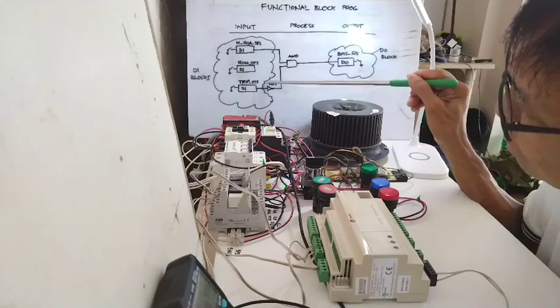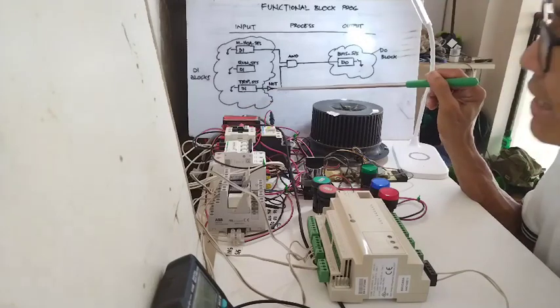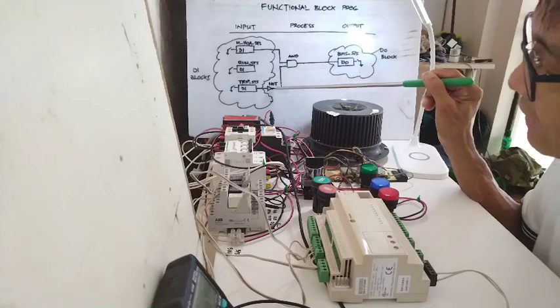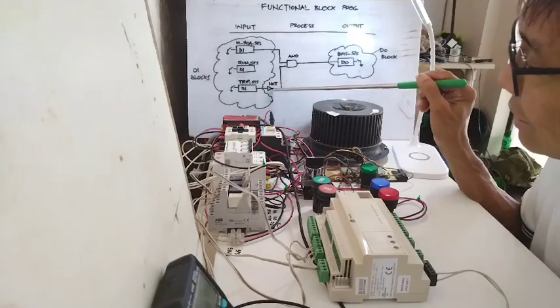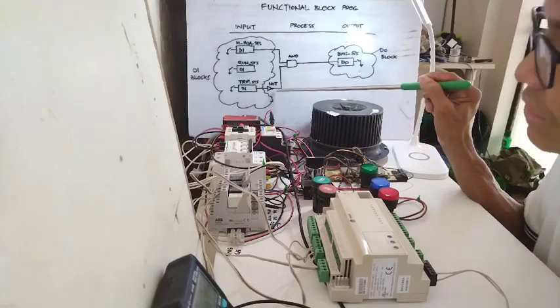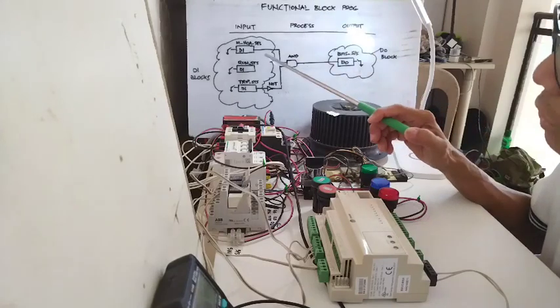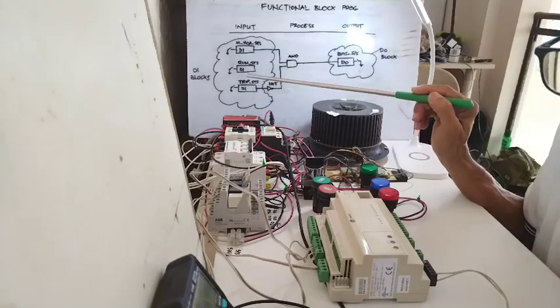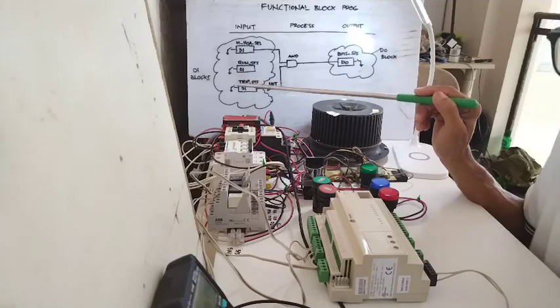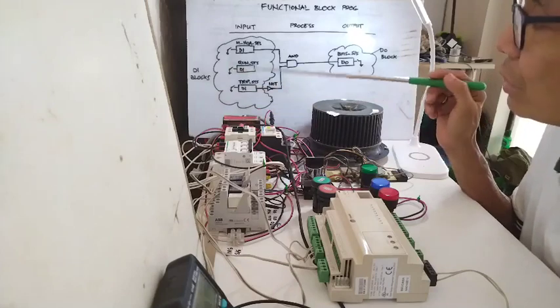I am using a NOT gate here, shown by a triangle with a dot in front of it. If the input is 1, it will be inverted to 0. If the input is 0, it will be inverted to 1. The condition to start the motor is: it must be in auto and there must be no problem with the motor. Obviously, you cannot start a motor when it is in a trip condition — it should not be in a trip condition before you can start it.